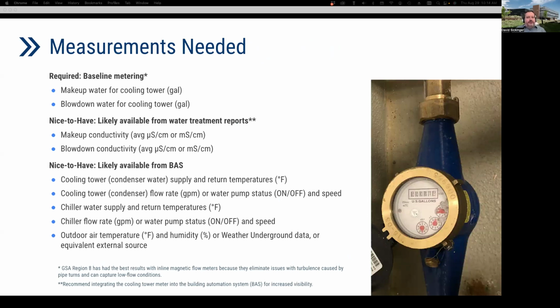So in terms of the measurements that are needed, I suggest using this framework to establish the baseline and track your AWT performance. The required measurements that figure most into the verification of cooling tower water savings are blowdown and makeup water consumption. The next thing to track and meter is the water conductivity in both the makeup and blowdown. And then during our evaluations, the status of water pumps and chillers were also recorded, so we knew which equipment was operating, along with supply and return temperatures. So when we did our load calculations, we had something to compare to as we looked at the ambient temperature and humidity for the test site. Next slide, please.